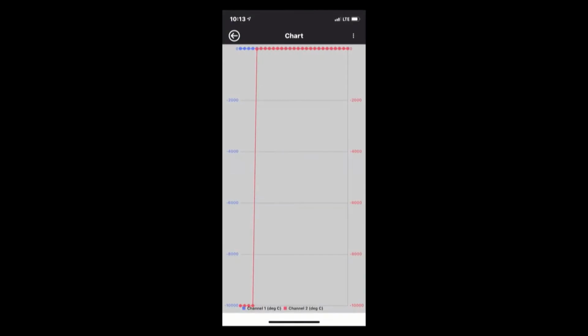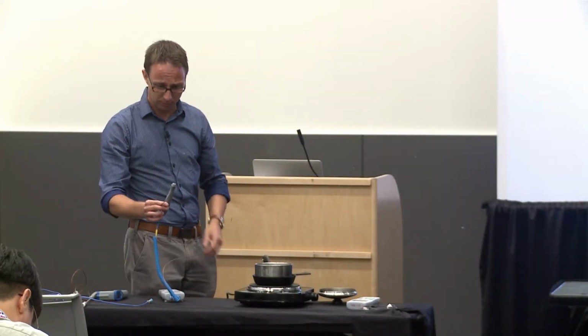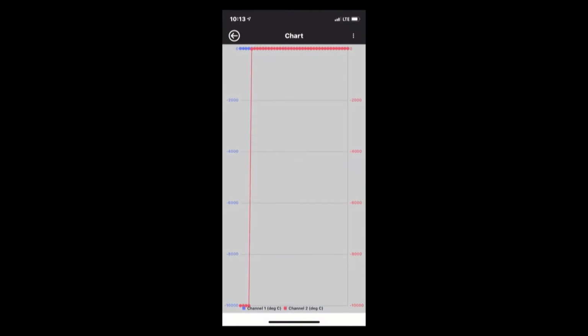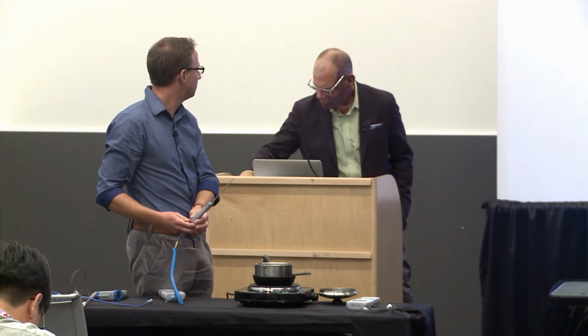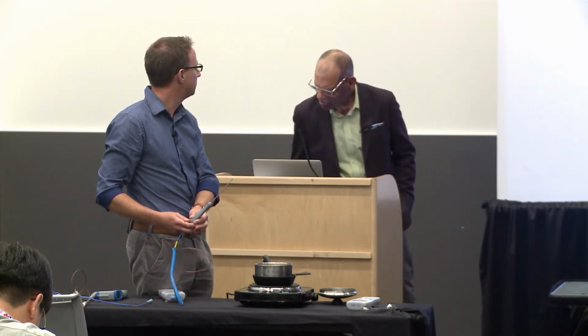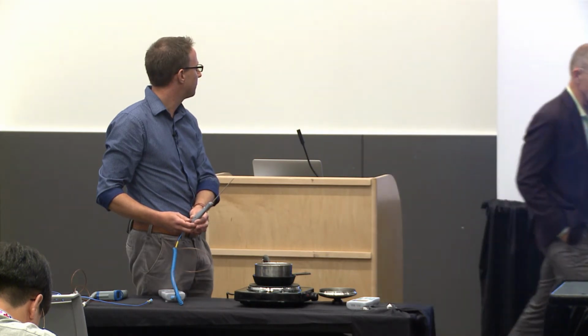So let's see here. So channel 1 is going to be our blue line, and in channel 1 I have connected an immersion probe, this is going to be an ungrounded tip with a sheath. Now in channel 2, I have a wire probe, and that's going to be an exposed thermocouple junction. You see the insulator and there's no sheath. I'm going to give this graph just a second to normalize. There you go. All right.